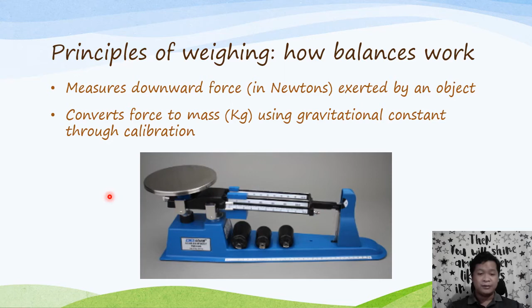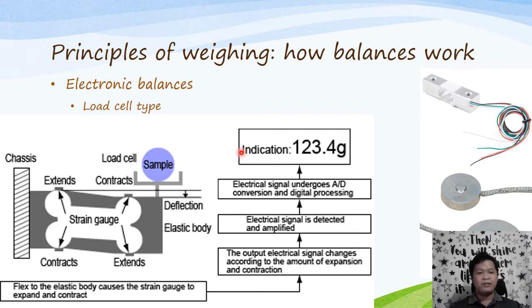So, how do electronic balances work? There are different types. Although I don't know if the load cell type can be considered a balance kasi it acts more like a scale, no, in a sense. But for the load cell type, you have a load cell, no, parang ganyan yung itsura nila. It's a strain gauge, so it measures forces applied to it para magbe-bend siya. And you measure that bending or deflection. Okay. So, pag may pinatong ka sample, the elastic body flexes in response to that sample. So it may expand or contract. And then the electric signal depends on how much that expansion or contraction is, and it's translated into an equivalent weight.